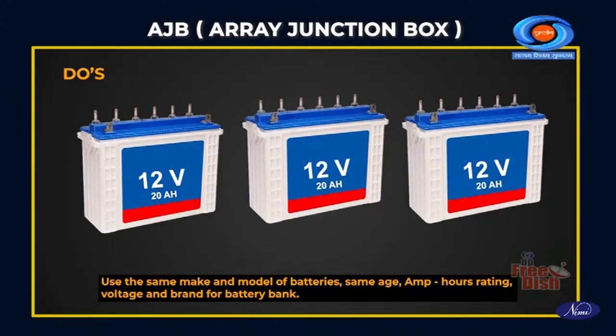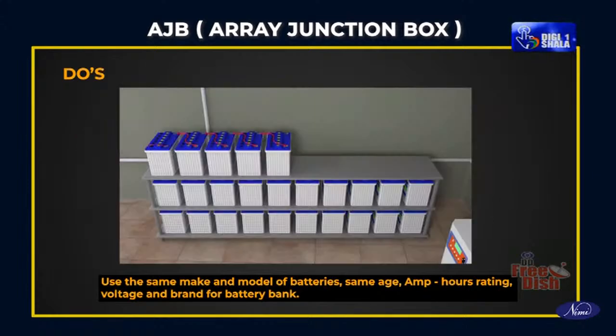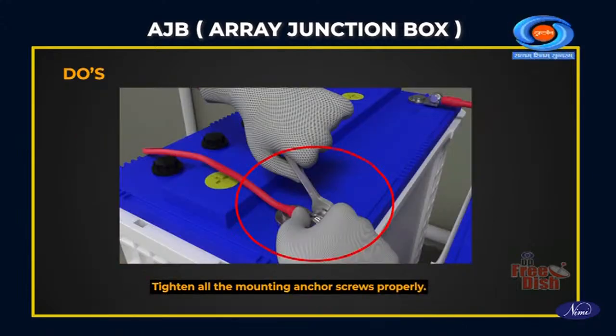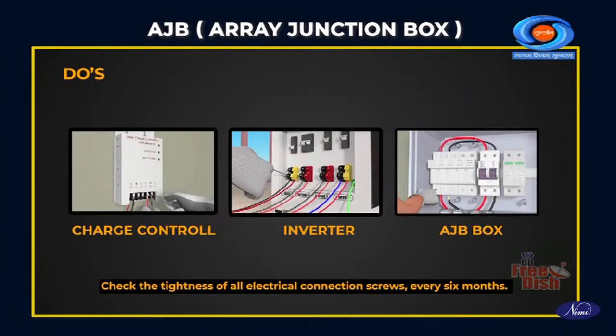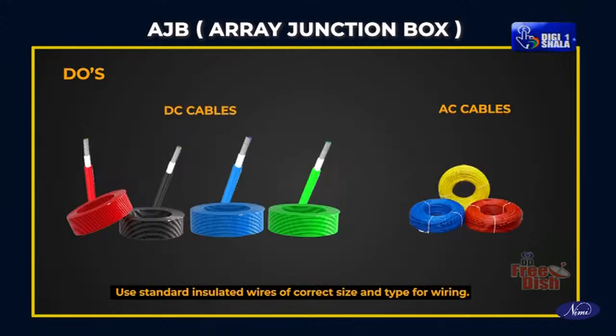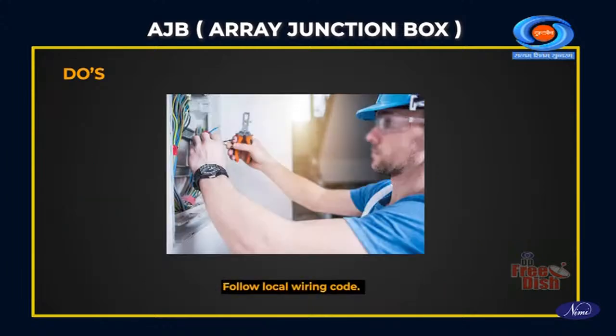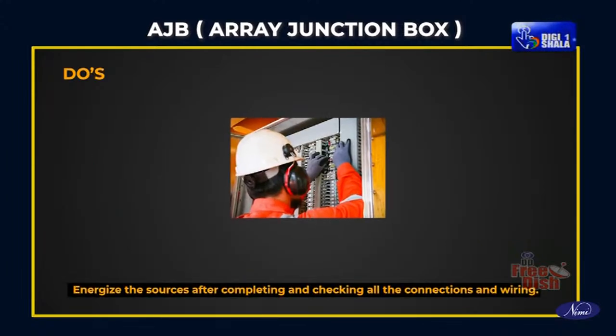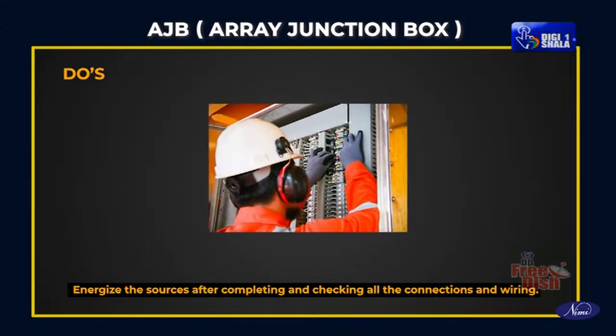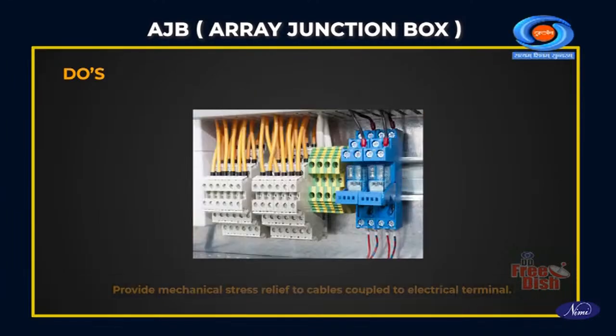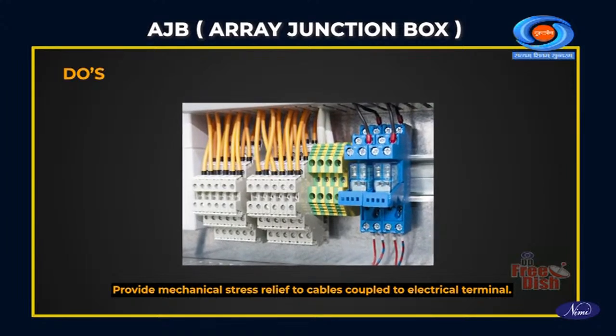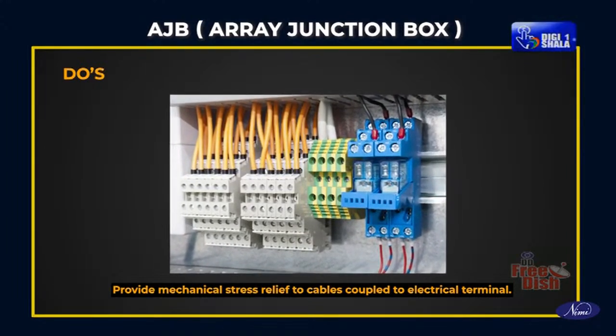Use the same make and model of batteries, of the same age, amp-hour rating, voltage and brand in the battery bank. Tighten all the mounting anchor screws properly. Check the tightness of all electrical connection screws every 6 months. Use standard insulated wires of correct size and type of wiring. Follow the local wiring code. Energize the source after completing and checking all the connections and wiring. Provide mechanical stress relief to cables coupled to electrical terminals.